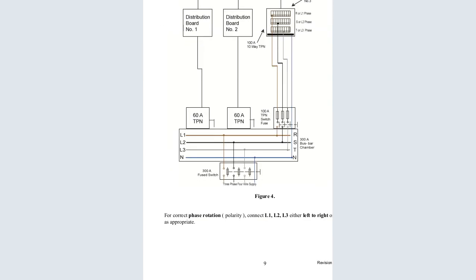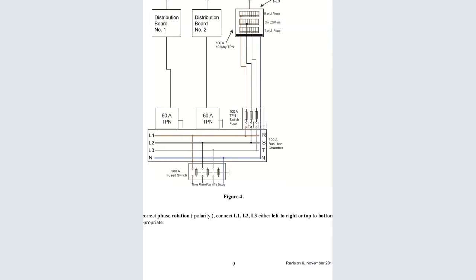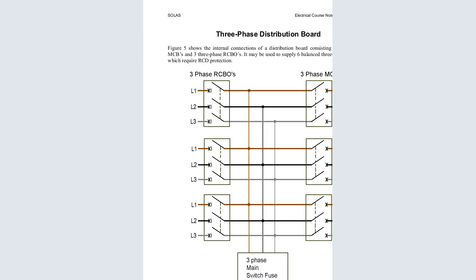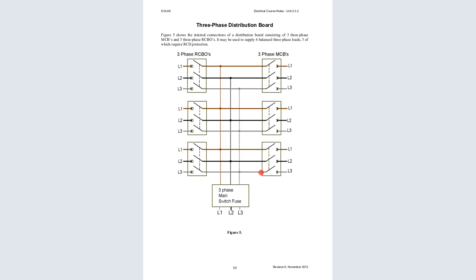You can see the correct phase rotation, that is polarity, and this is now balancing of the phases. Connect line 1, line 2, and line 3 either left to right or top to bottom, as appropriate. Now the 3-phase distribution board, how is it installed or how does it tap the wires? We said that figure 5 shows the internal connection of a distribution board consisting of 3-phase MCBs and 3-phase RCBOs. It may be used to supply 6 balanced 3-phase loads, 3 of which require RCD protection.